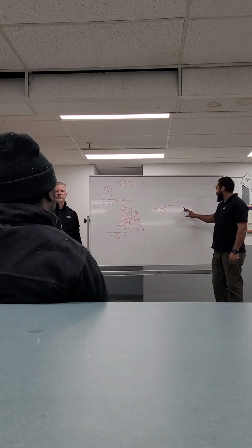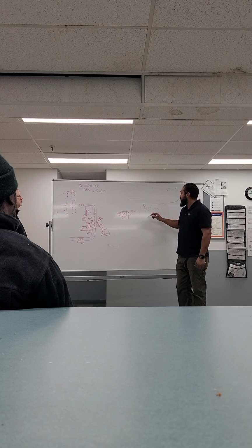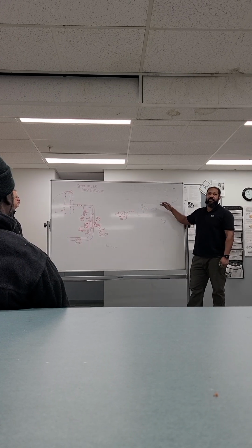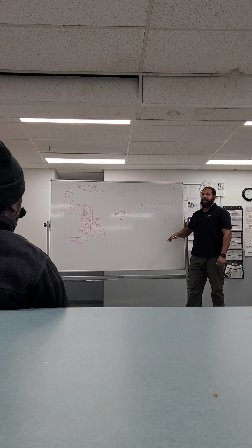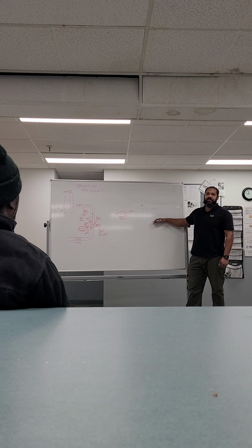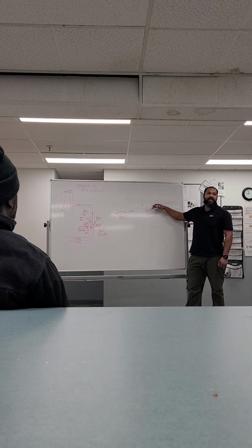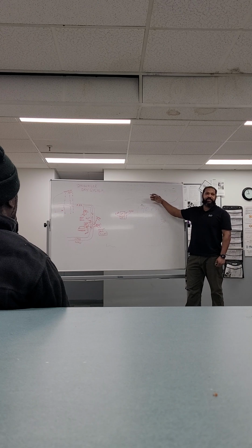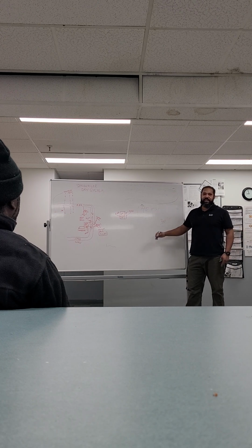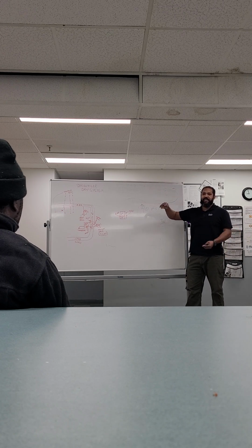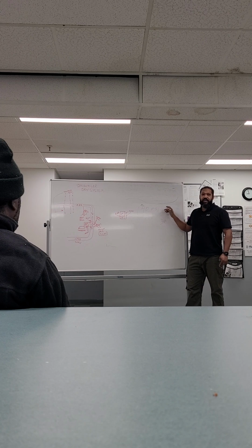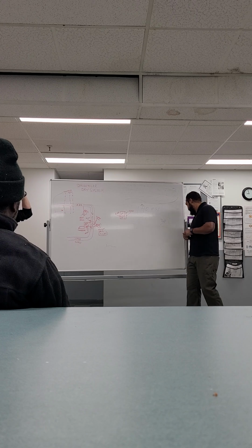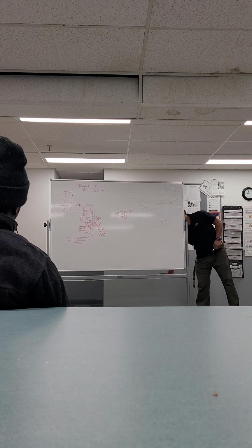But you still have that number, so you calculate 5 PSI per floor. You have some basement, 5, you have first floor, 10, you have second floor, 15, you have fourth floor, 20. So basically you still have 20 PSI above, which is good. Now, why we have pumps here is because we have too many floors and too many apartments, but there's a difference between water pressure and volume of water. So that's why we have some pumps, because we need more pressure and we need more volume. Anything over a certain number of stories has to have a fire pump to push that up there.